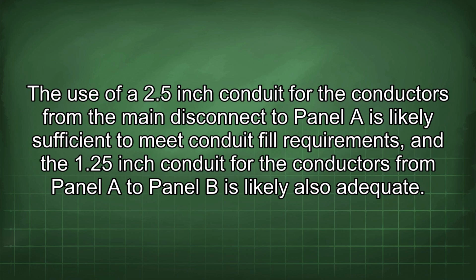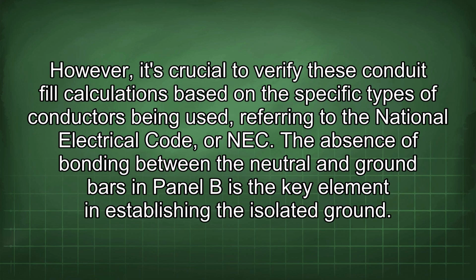The use of a 2.5-inch conduit for the conductors from the main disconnect to panel A is likely sufficient to meet conduit fill requirements, and the 1.25-inch conduit for the conductors from panel A to panel B is likely also adequate. However, it's crucial to verify these conduit fill calculations based on the specific types of conductors being used, referring to the National Electrical Code, or NEC.